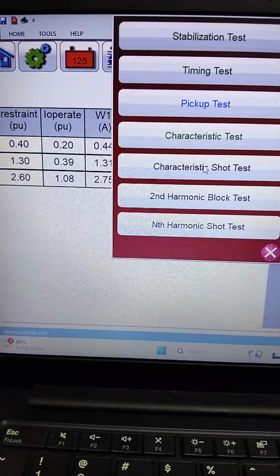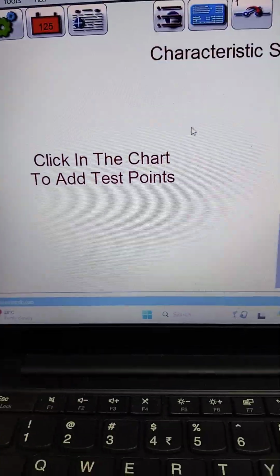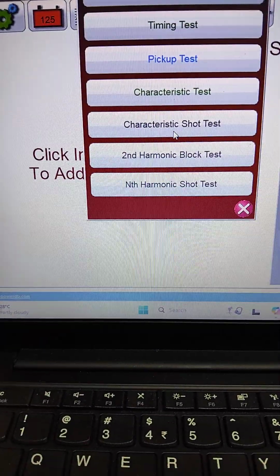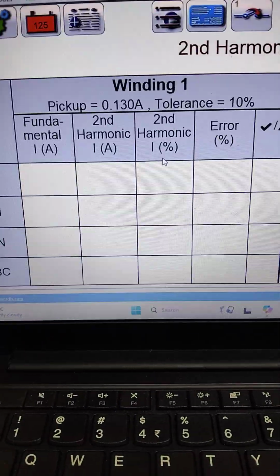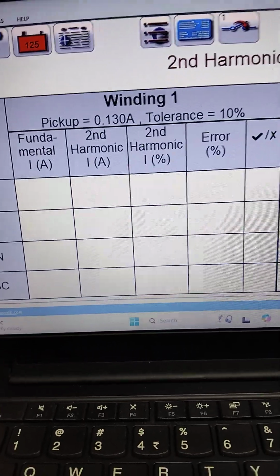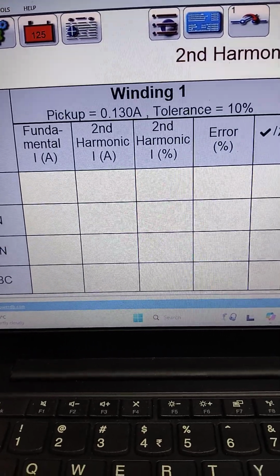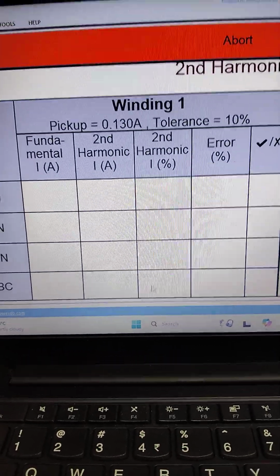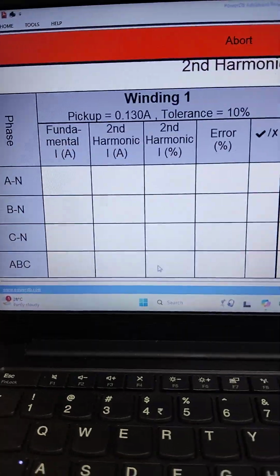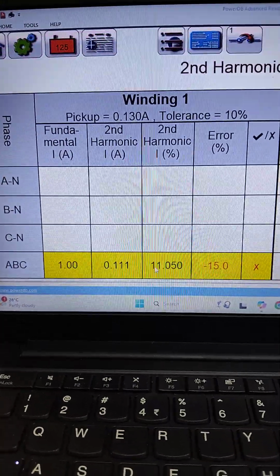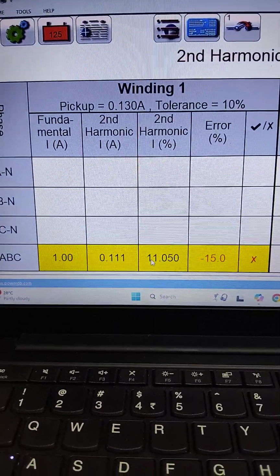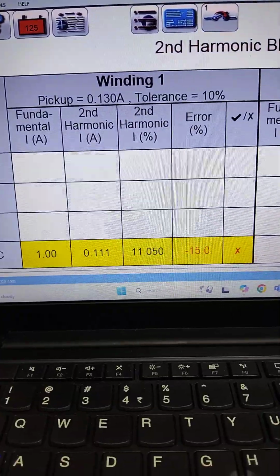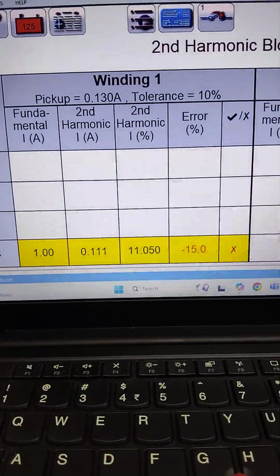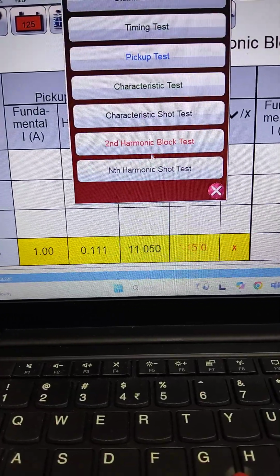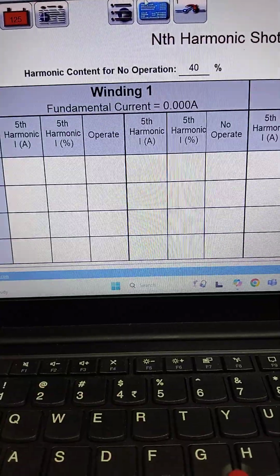So again there is a second harmonic testing. In this, basically it injects some current, and it's a mix of second harmonic and your primary value, and it will expect a trip, but I think we need to check it. Then you can check the shot characteristics.